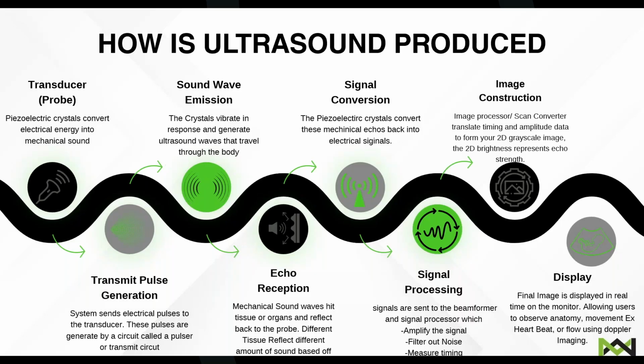Once the sound waves travel through the body and deflect off of organs or tissues, they reflect back. We call this reflection echo reception. Different tissues reflect different amounts of sound based off of density and composition. When this sound echo comes back to the ultrasound probe, it hits the piezoelectric crystals and converts these mechanical echoes back into electronic signals again. These electronic signals are then processed in a process we call signal processing. They go through the ultrasound system and hit the beamformer, which amplifies the signals, filters out the noise, measures timing, and determines signal strength.